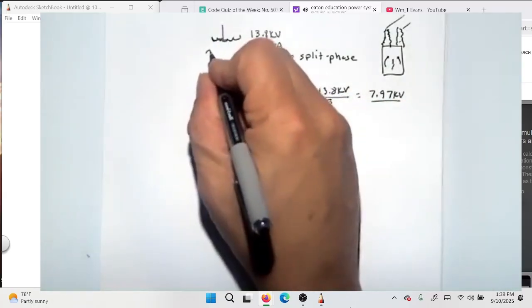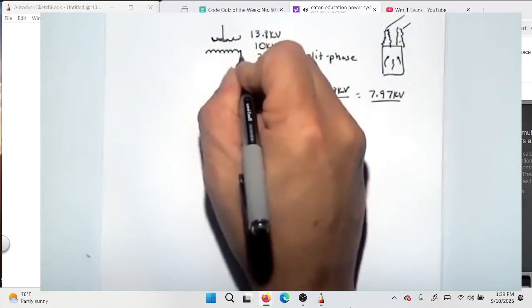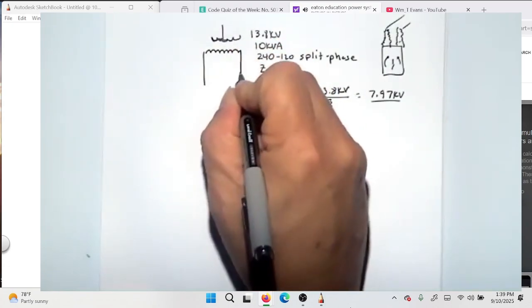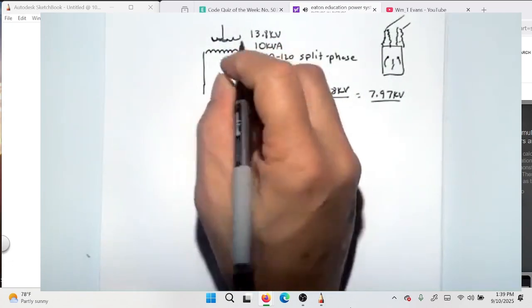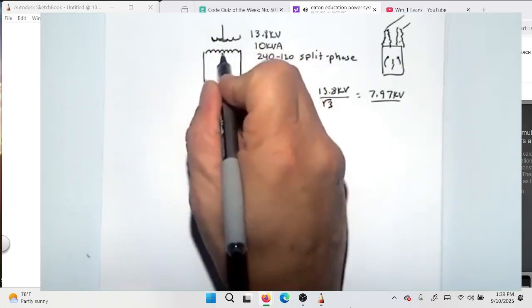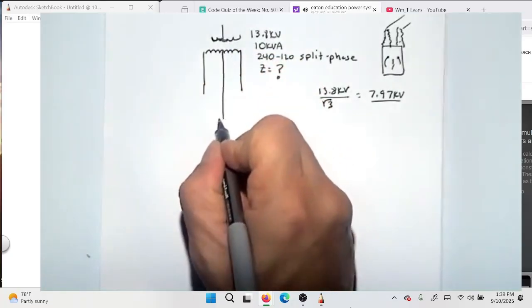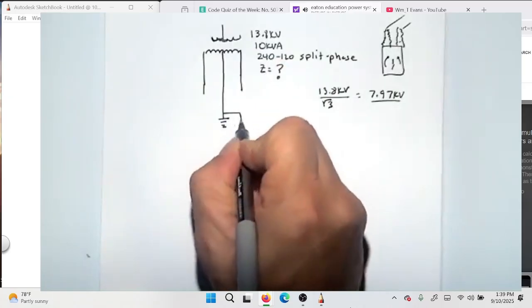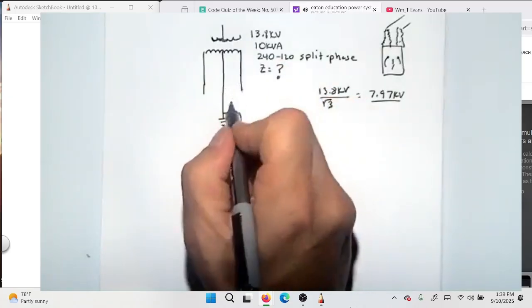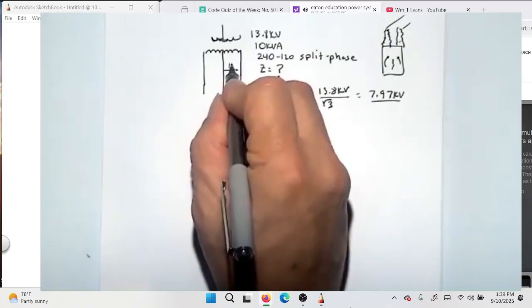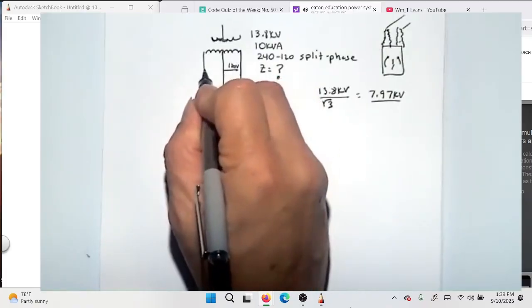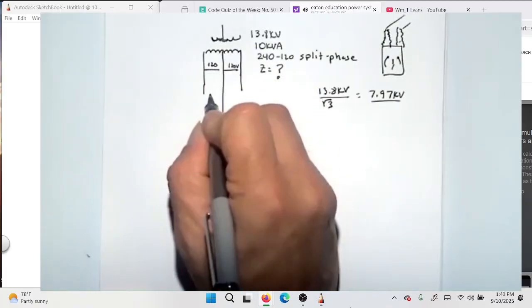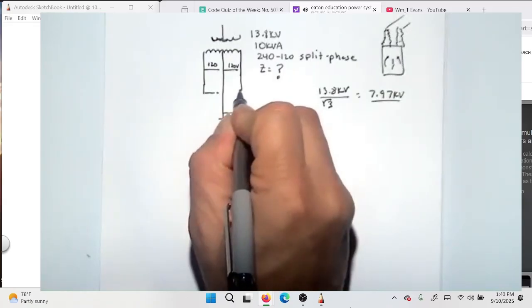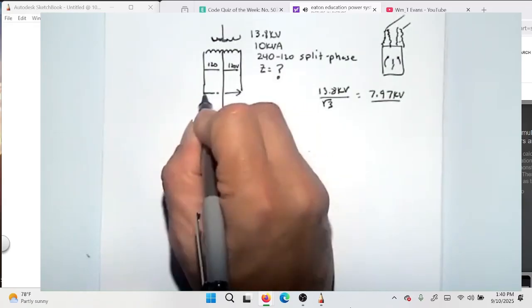The secondary of the transformer looks like this. These 2 windings coming off of there are 120 volt to a grounded neutral. So the neutral is grounded. It's brought into your home. And so it's 120 volt here, 120 volt here, and then 240 volt from here to here.